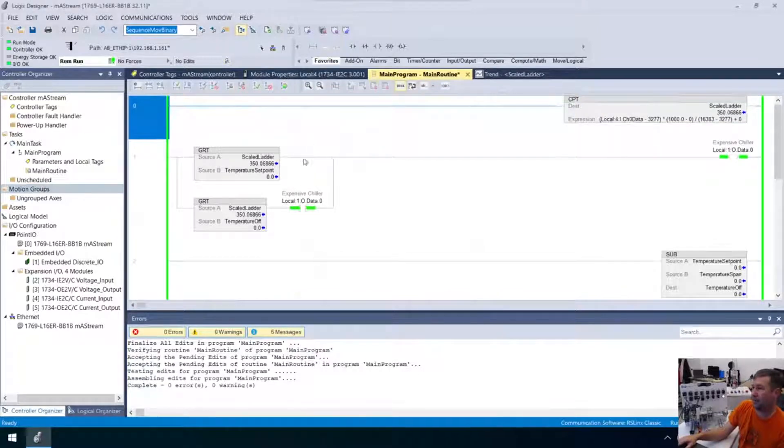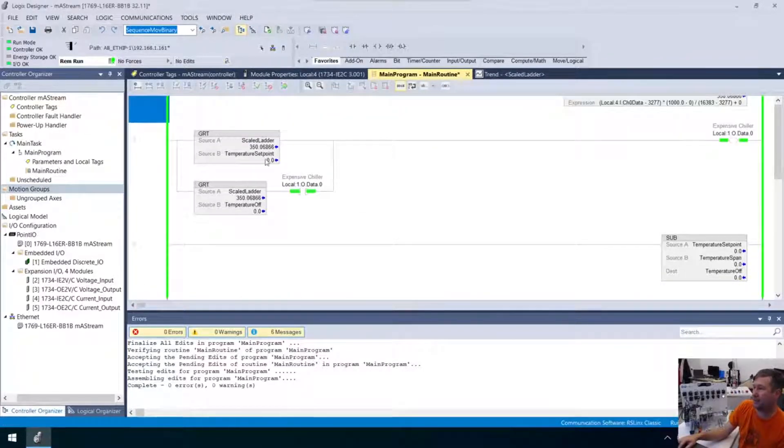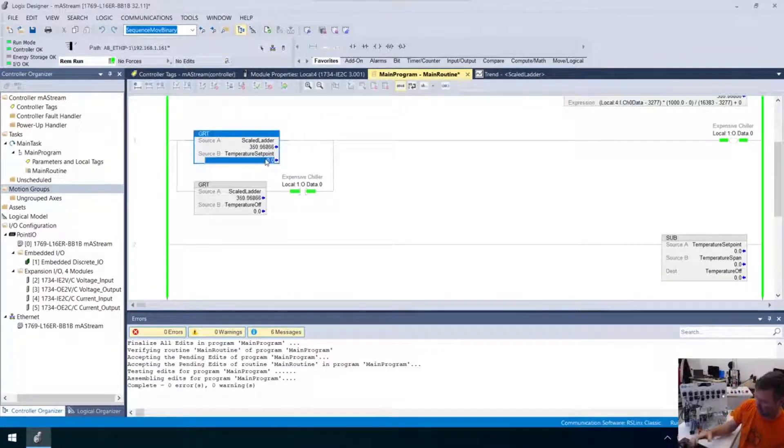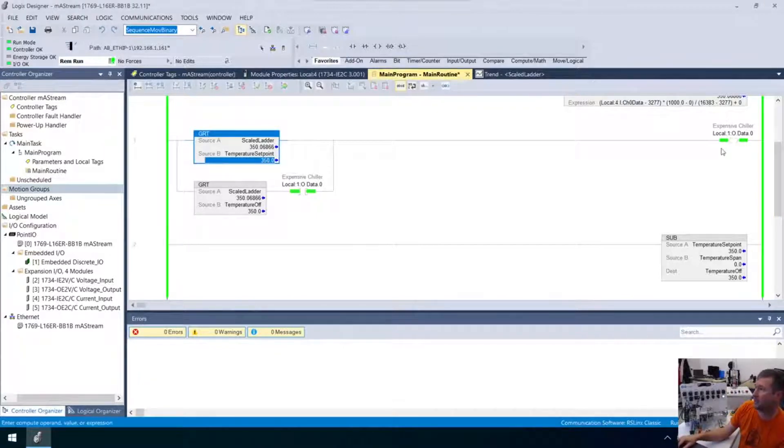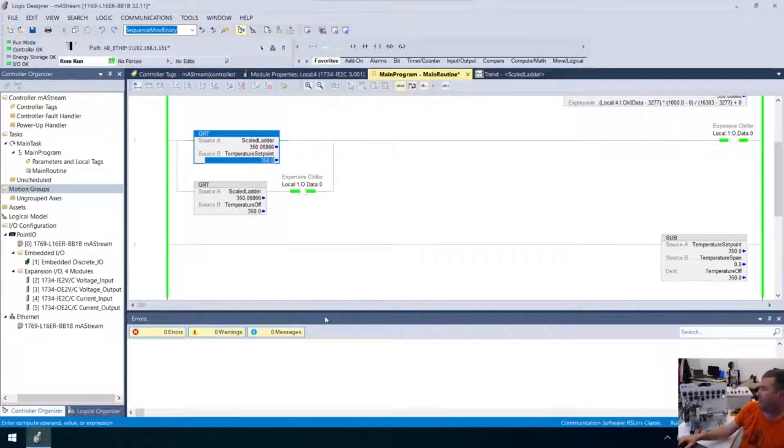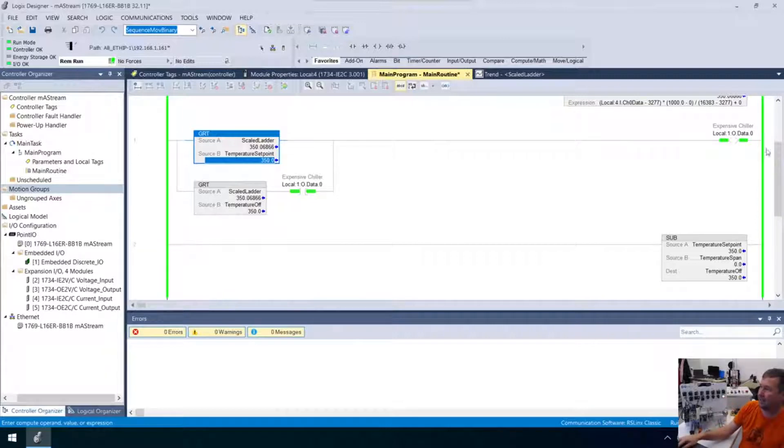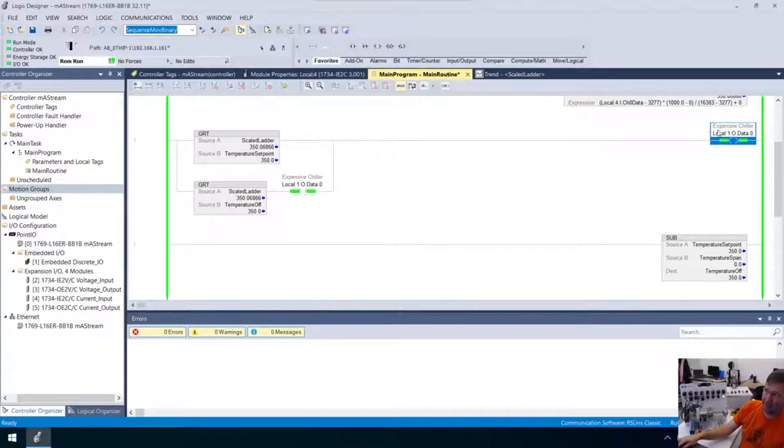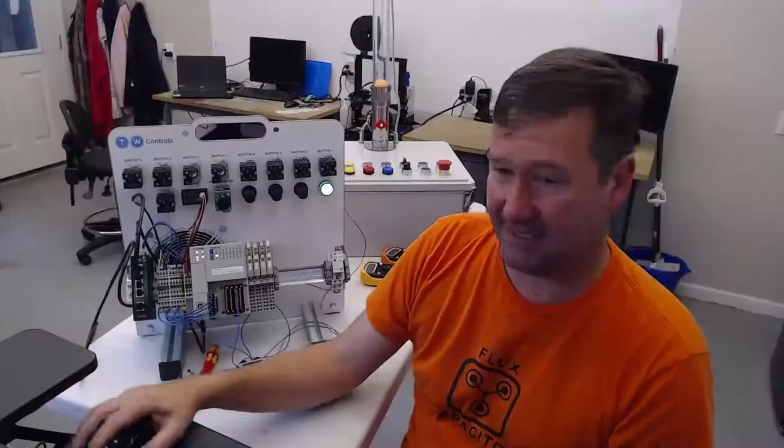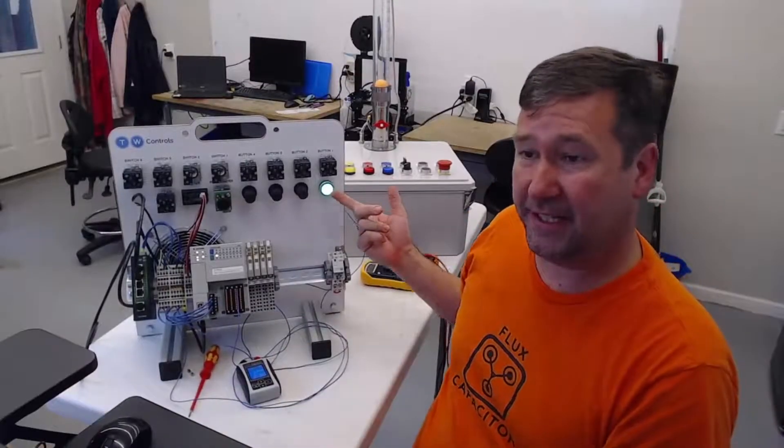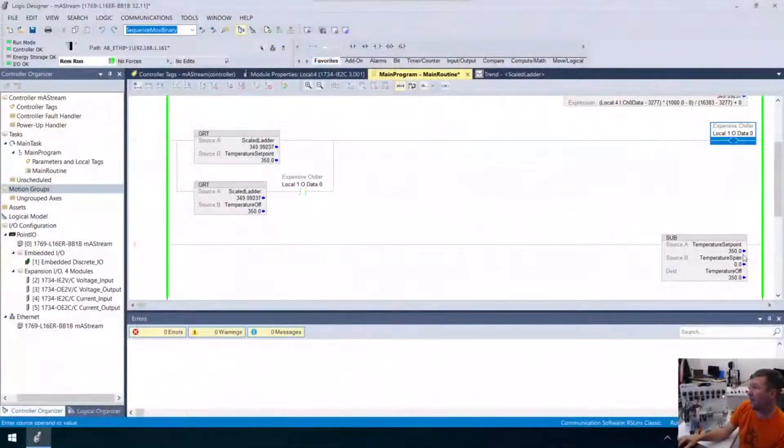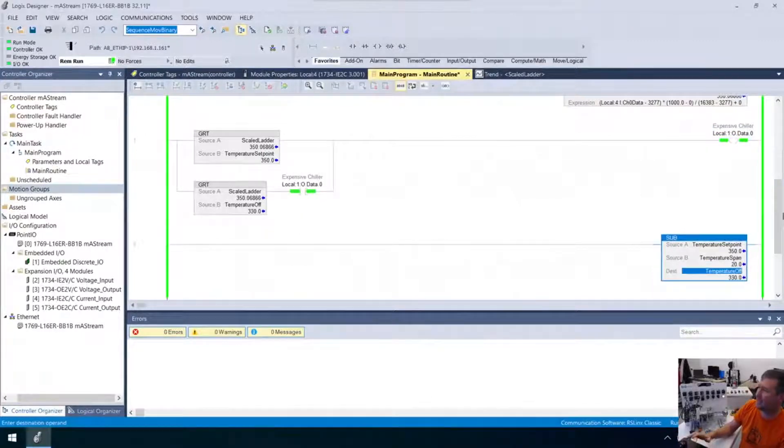And okay, so one, let's put this in just like it is, just so you see it's going to do the exact same thing right now. Because, oh, I made a mistake here. Anybody catch it? Actually, in a crazy sense, this actually would work. But there's a problem here. This is only going to do this subtract when one of these statements are true. That's not good. That can cause us some issues. So either this needs to be around the whole thing or on its own rung. So I'm going to bring another rung down. And I'm just going to drag this subtract. Come on, my computer's choking up on me. Bring the subtract down to here. That's what I should have done. Take that branch out. That way our span is always calculated.